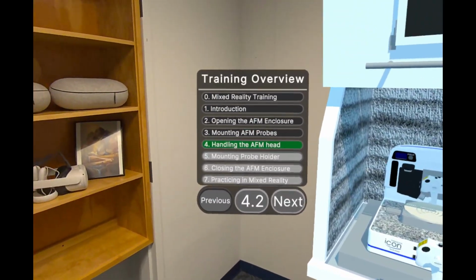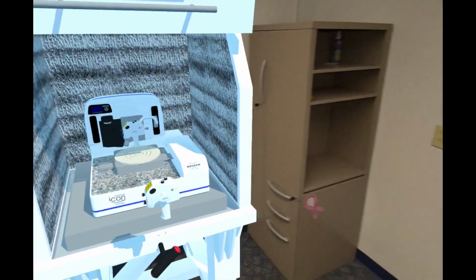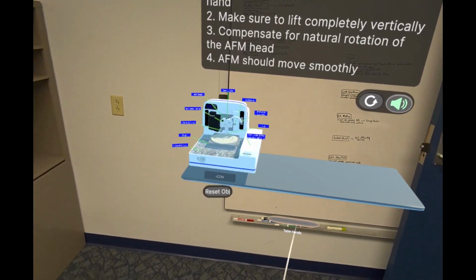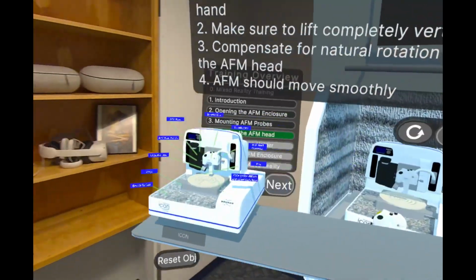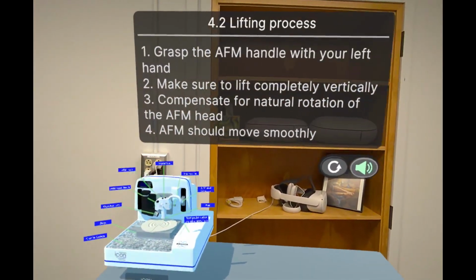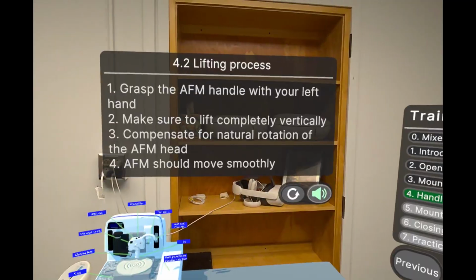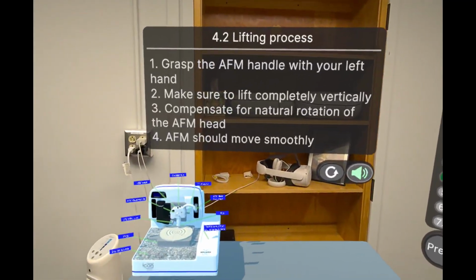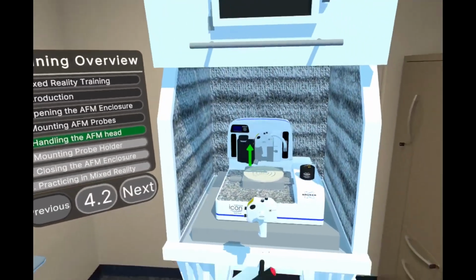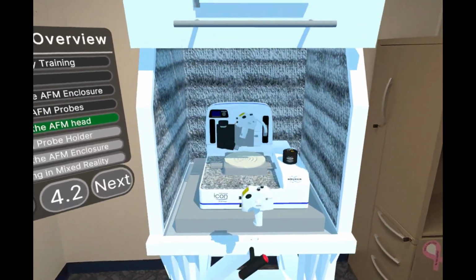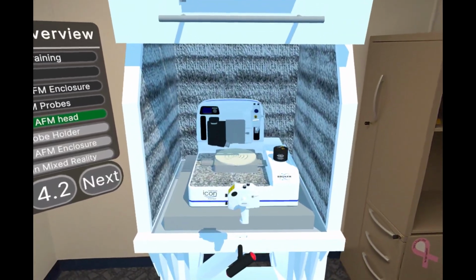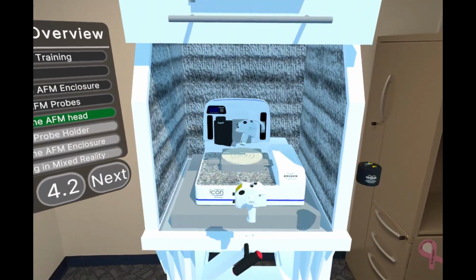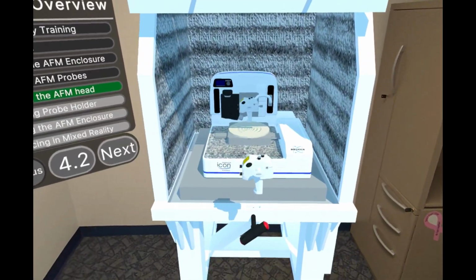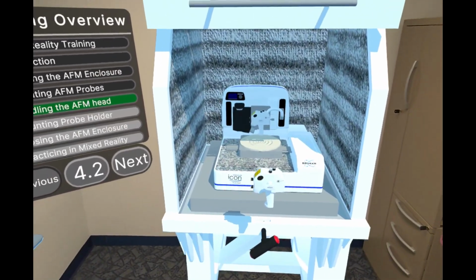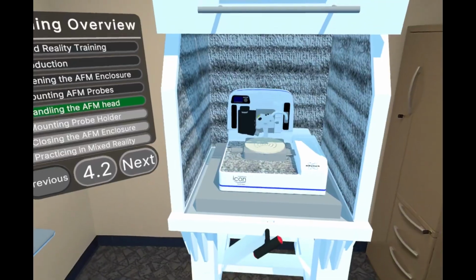Before lifting the AFM head out, make sure the area is clear. Next, unscrew the thumb screw just a few turns. Notice that the AFM head is mounted in a dovetail slot. It has very tight tolerances, which means that it needs to be lifted straight up, vertically, like an elevator. While lifting, if you introduce even slight rotations about any axis, the AFM head will not lift up.